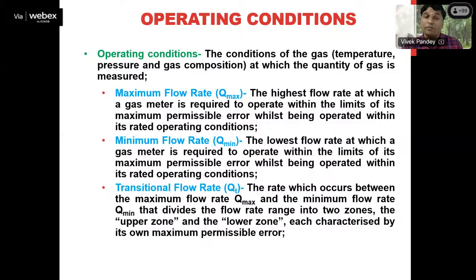Now within this minimum to maximum flow rate, there is one more flow rate specified in our rule, that is the transitional flow rate. From the name it is clear that it is a point within the minimum to maximum flow rate where a certain transition or change is happening. And that transition is what? The transition of accuracy. Fine.